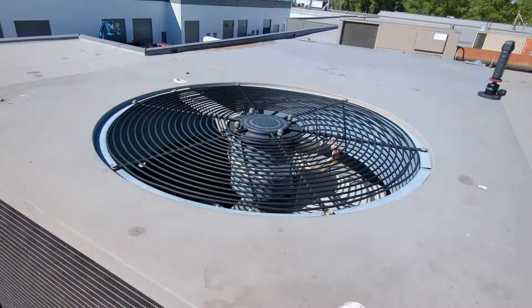Coil cleaning number two — this is at the Old Spaghetti Factory where I have to go up that little staircase and out the window. Let's cut power to the unit first. This is where I'm going to use my hand pump because I'm going to use chemicals on this condenser coil. I'm going to be using Nu-Calgon's Nu-Brite condenser coil cleaner, which turns quite foamy once it hits the dirt — it's really satisfying to watch all that dirt fly away. It's already starting to foam up and it's going to need about 10 minutes to sit.